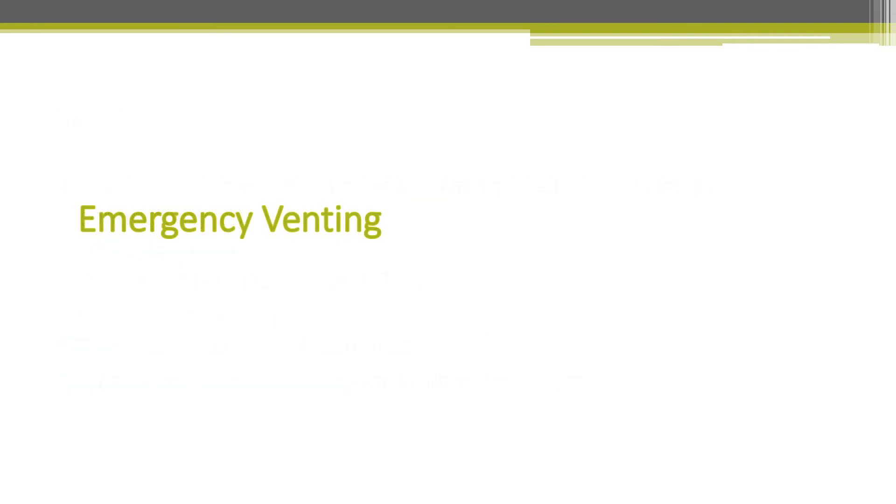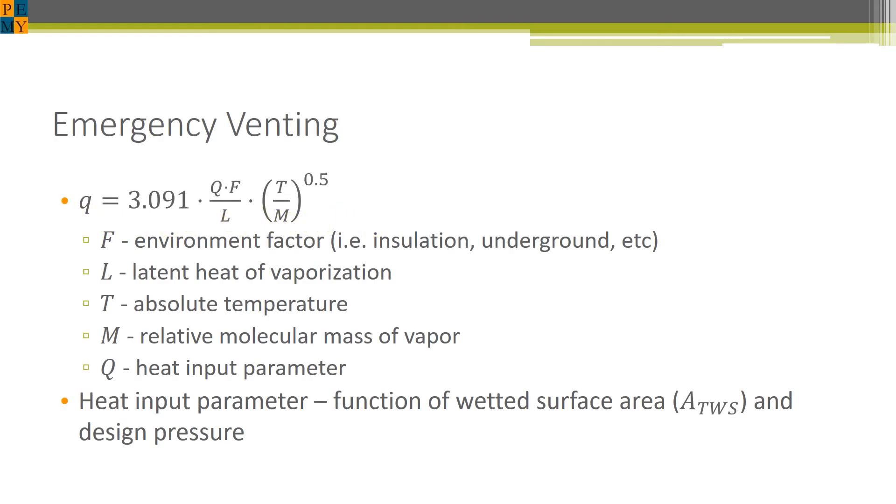That's it for normal venting. We will now consider the condition of emergency venting. For emergency venting, it is a heat flux equation where we determine the amount of heat flow that's generated from that adjacent fire into the tank. We have different properties like the latent heat of vaporization, the temperature, the relative molecular mass, and the heat input parameter, which is a function of the wetted surface area of the tank and the design pressure. Essentially, how much of the tank is actually exposed to the fire. This is dependent on engineering judgment.